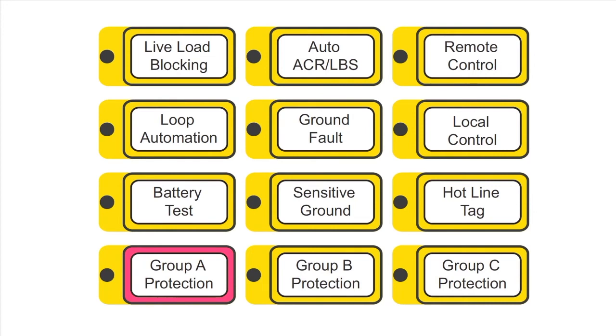Group protection A, B, or C. These three keys activate the settings configured in protection group A, B, or C one at a time. The user can quickly access any of the pre-programmed setups. A red lamp indicator shows when the function is on. Auto ACR LBS. The key toggles the Auto Reclose for reclosers or the Sectionalize Auto feature for sectionalizers on or off. A red lamp indicator shows when Auto is on.